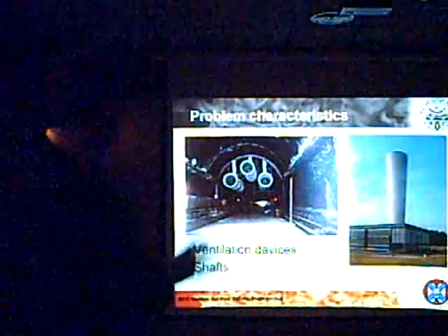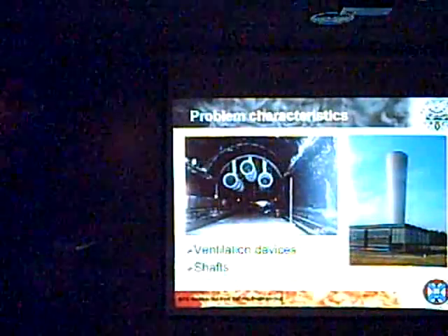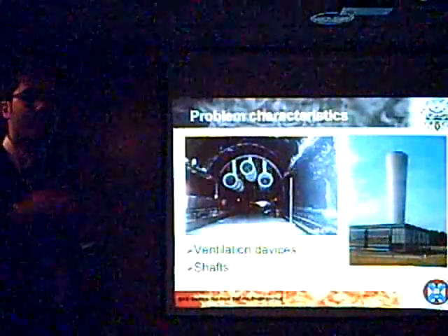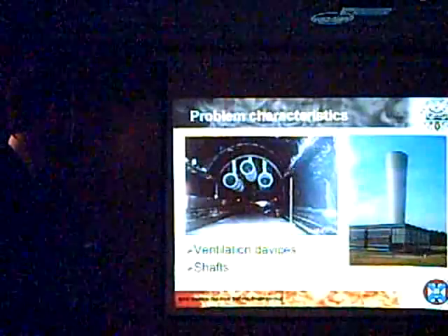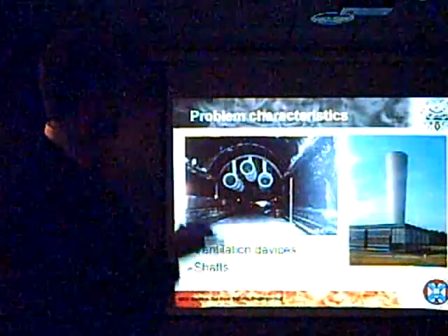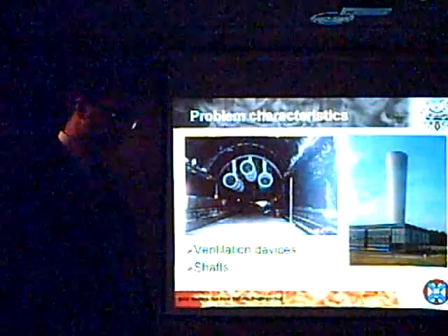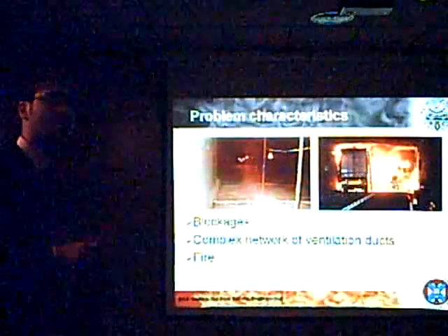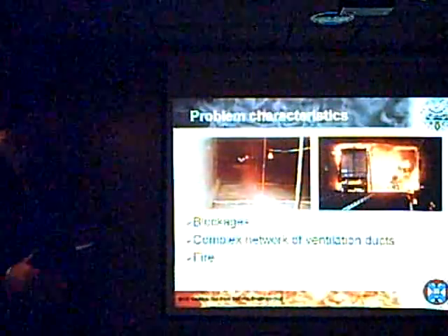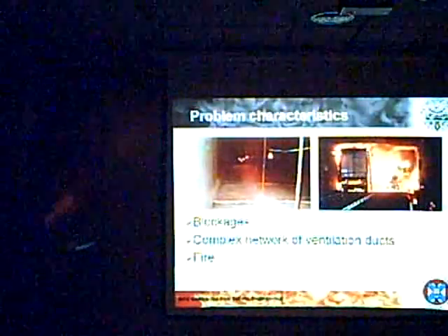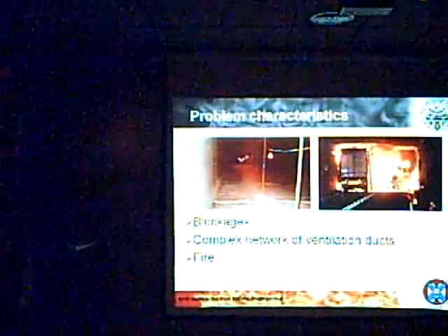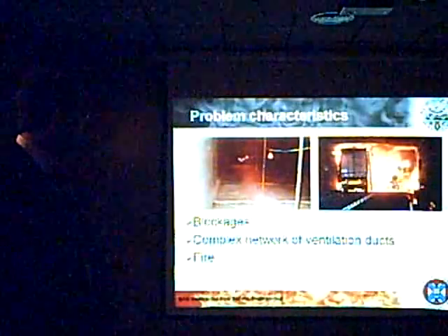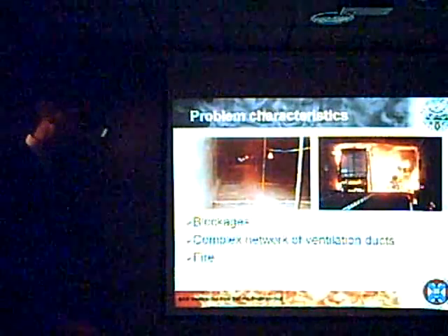When we talk about tunnel, we have to deal with ventilation devices, we have to know how to model the jet fan, and we have to deal with boundary conditions that can vary during our simulation. We have to deal with shafts, so we should know the boundary condition and the temperature on the top of the shaft. Within the tunnel we can have blockages like cars, like trucks, like in the worst case scenario a traffic jam. We should know how to deal with the complex network of ventilation ducts, above all for transversely ventilated tunnels. And we have to deal with the fire, with its size and location.